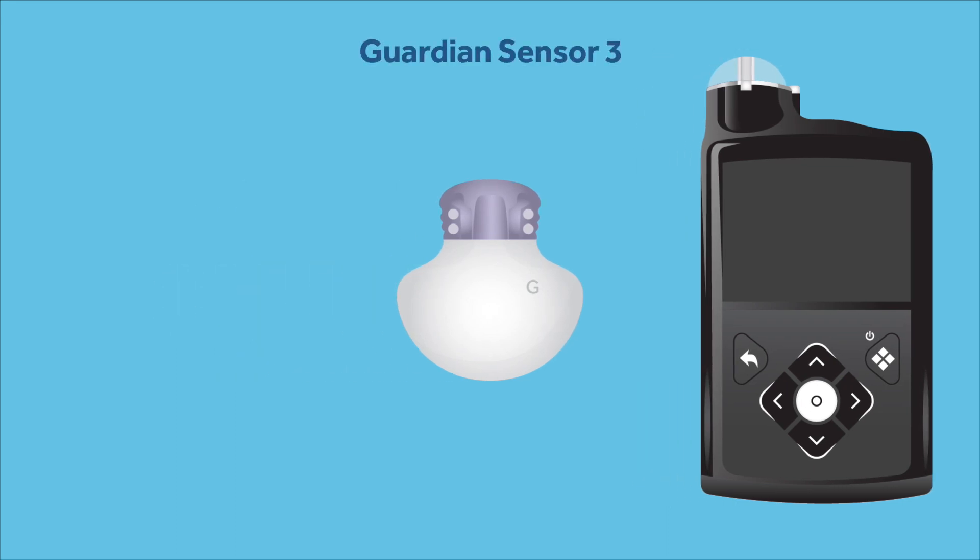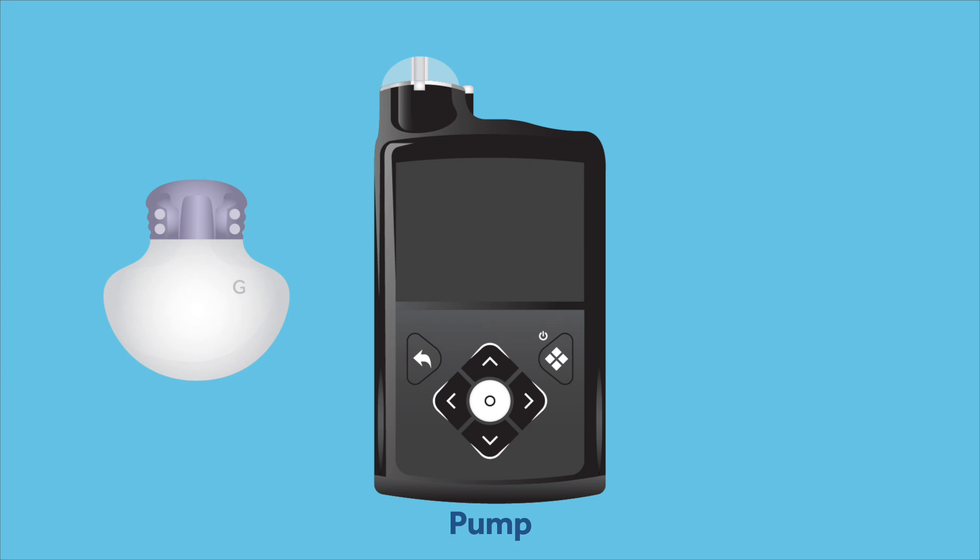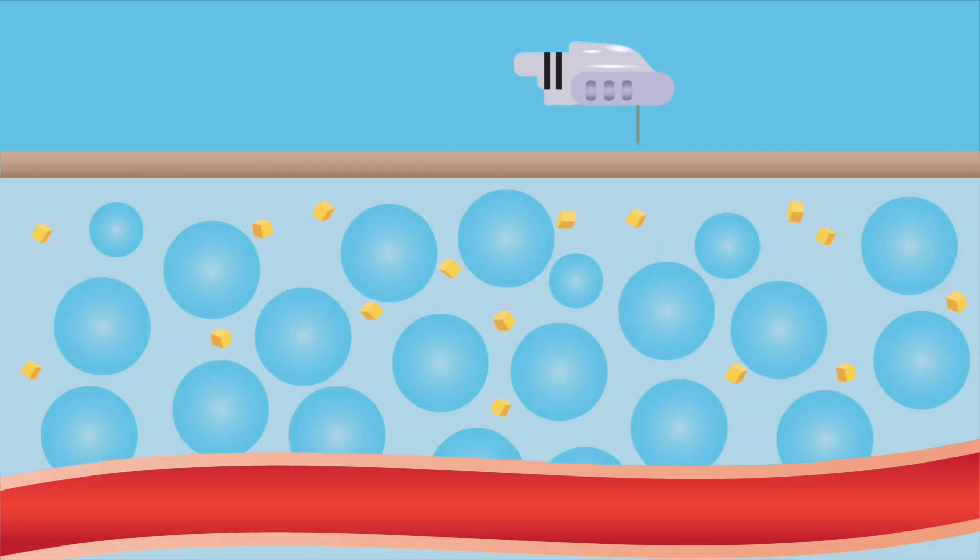The Guardian Sensor 3, the Guardian Link 3 transmitter, and the Minimed 770G insulin pump. The sensor is inserted into the skin so it comes into contact with the fluid beneath the skin. The transmitter is then connected to the sensor. Every five minutes, the sensor measures the glucose found in the fluid under the skin and sends that information through the transmitter to the pump. The glucose value then appears on Lisa's pump.